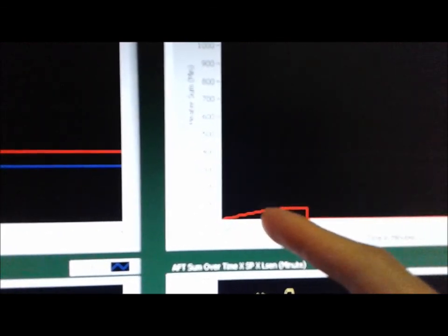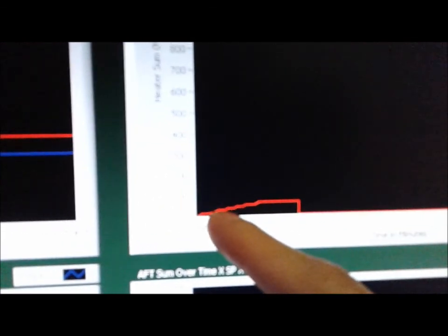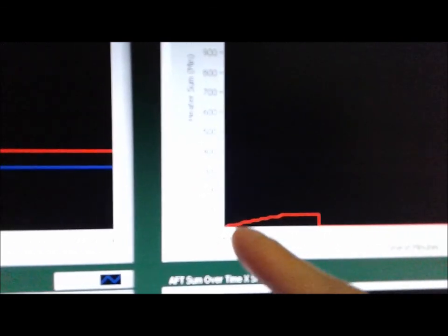And here's the heater chart for tank 2. Actually, we can see here that it's quite easy to maintain the temperature. The controller starts the heater just a tiny amount of time, then a line here, then a line, another step up, line, step up, line, step up.